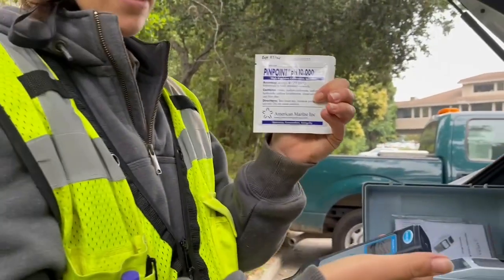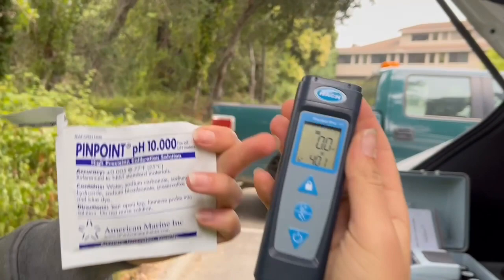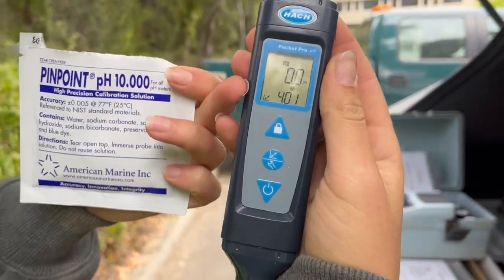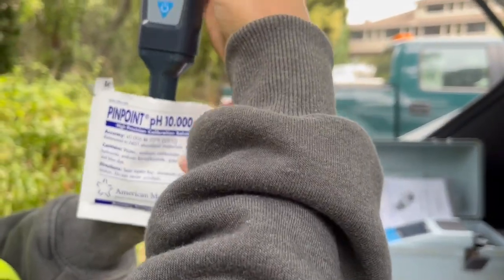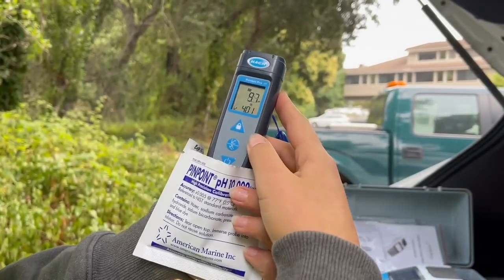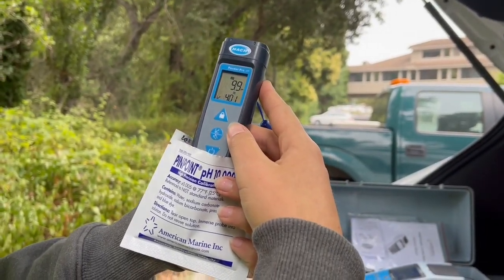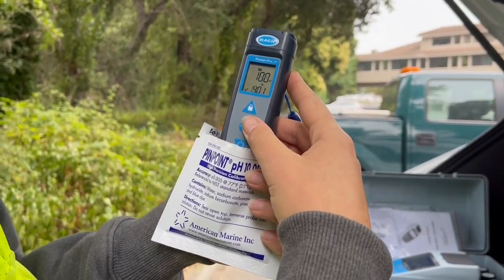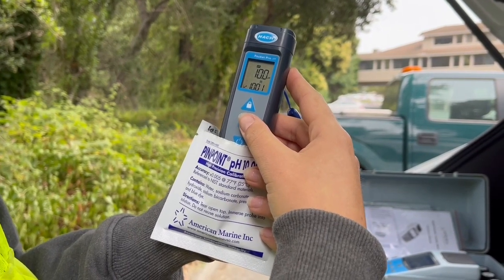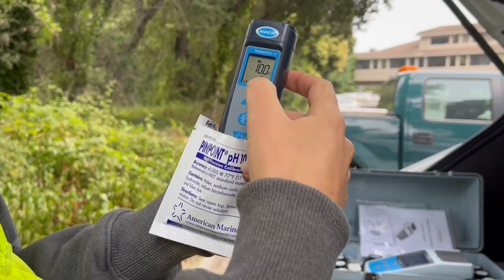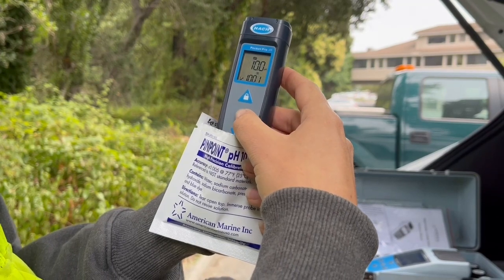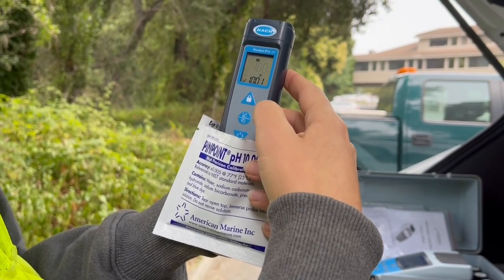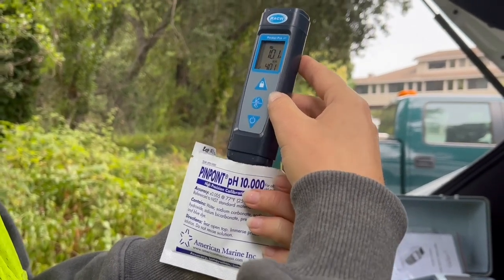So I'm going to set aside my pH 7.0 solution and go for either 4 or 10. I pulled out the 10. So if you look at the face of the probe now, it's flashing between 4 and 10. I've opened the pH 10 packet. I'm just going to insert it in. It gets close to 10. Once it stabilizes, and once that bottom reading also stabilizes to 10, I'll press calibrate. It'll flash, and then I'll be done.